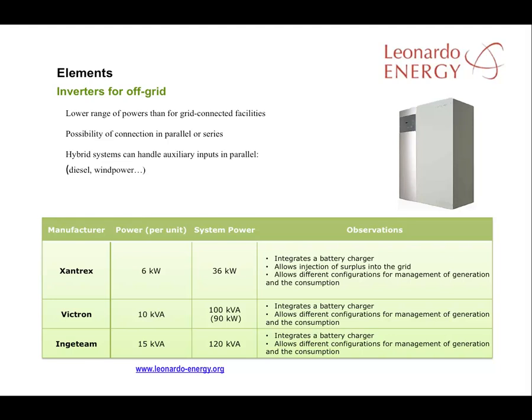This slide includes some of the offerings from the main manufacturers of this kind of inverter: Xantrex, Victron, and Ingeteam. If you check the values in this table, you will see that the power per unit is extremely low — from 6 kW to 15 kVA. But the system power is a little higher because it is possible to connect several inverters: with Xantrex, 6 inverters in parallel or series; with Victron, 10 inverters; or with Ingeteam, 8 inverters.